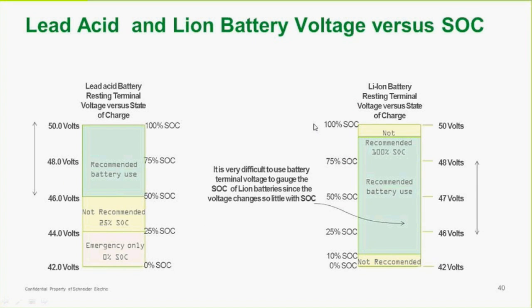And then there's lithium ion versus lead acid. There are definitely different characteristics between them. As you can see, there's a limited amount of use from lead acid batteries, and this may go down typically to 44 volts. So we have a voltage range of 50 from 44, so we can tell the state of charge very easily on a lead acid battery. But 44 is basically the cutoff where you still have a 25% state of charge left. With a lithium-ion battery, you can run it down quite a bit further, depending on the manufacturer. As you can see from this graph, you can run it down to 10% state of charge. The interesting thing about lithium-ion batteries is that the output voltage remains fairly flat, and that's why it takes a different setup to monitor them accurately.